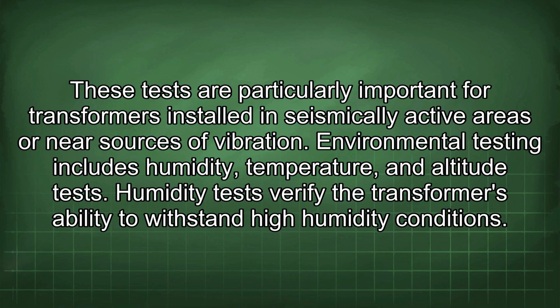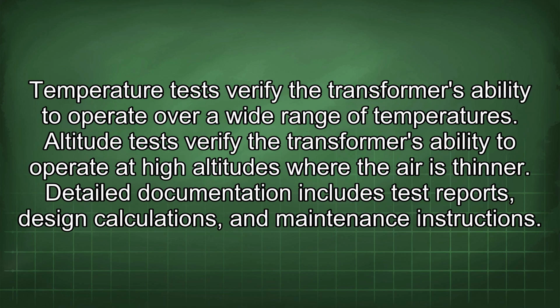Environmental testing includes humidity, temperature, and altitude tests. Humidity tests verify the transformer's ability to withstand high humidity conditions. Temperature tests verify the transformer's ability to operate over a wide range of temperatures. Altitude tests verify the transformer's ability to operate at high altitudes where the air is thinner.